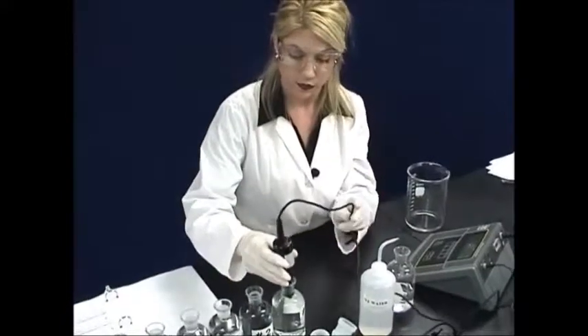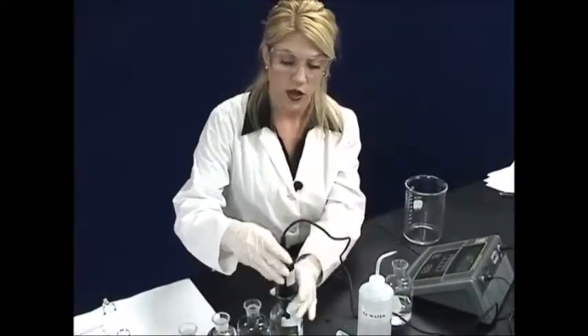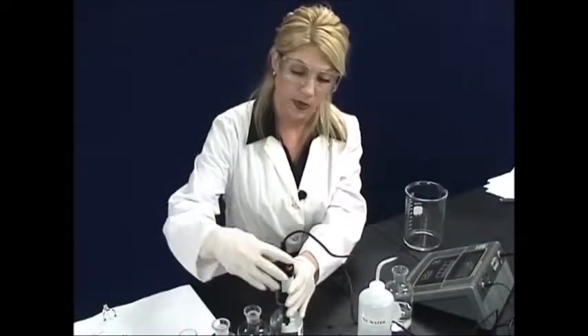Next, we will come over to our calibrated dissolved oxygen meter. Make sure that your DO meter is calibrated according to the manufacturer's specifications. Once you have done this, you will take the clean probe of your DO meter and place it in the first bottle to be read. I'm going to turn the stir on our probe. We have an automatic DO meter. If you do not have an automatic stir on your DO meter, you will want to use a magnetic stir bar in each of the BOD bottles and place them on a stir plate.